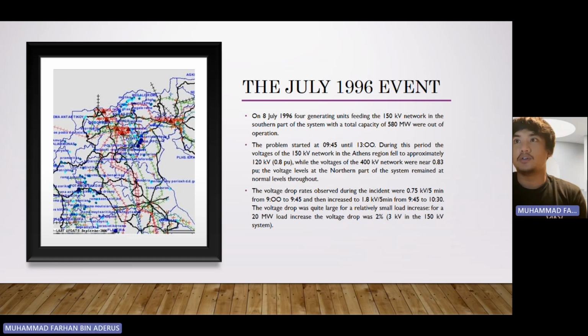The voltage level at the northern part of the system remained at the normal level. The voltage drop rates observed during the incident were 0.75 kV per 5 minutes from 9 am to 9:45 am, and then increased to 1.8 kilovolt per 5 minutes from 9:45 am to 10:30 am.